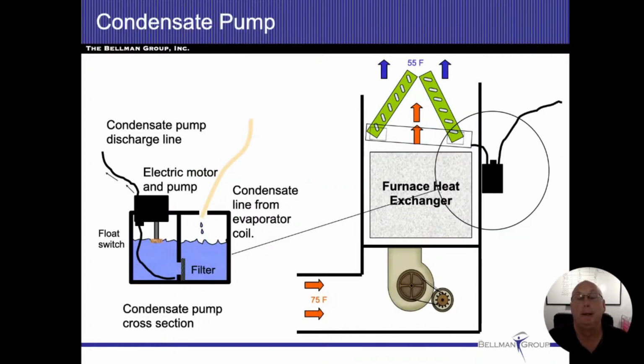Sometimes we don't have a floor drain near us, and if that's the case, we have to put a condensate pump in there. It's going to be difficult. Sometimes you could stick your finger in there and trip the pump to see if it works. But in all reality, if the air conditioner has been running and you're in the summertime, you'd have water all over the floor if it wasn't working. So that's going to be our number one clue.